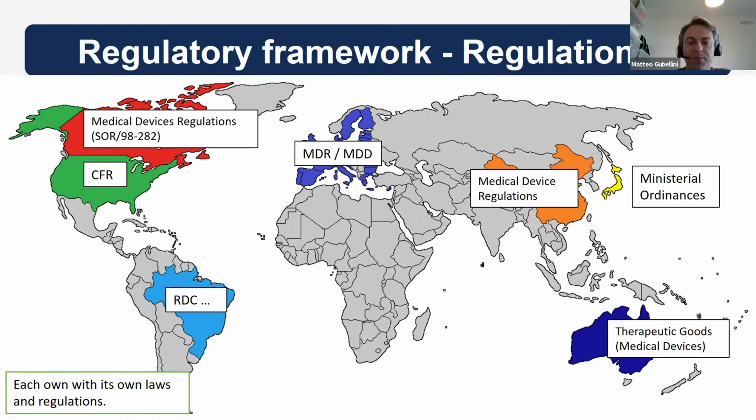They are, in most cases, promoted and signed by the government. In Europe, it was the European Parliament. But this is very much country or jurisdiction specific, and something that is required in one jurisdiction is not necessarily required in other ones. They go into a level of detail like classification of devices, post-market surveillance, the way to register a device, the way to report adverse events, complaints, things like that, which are very specific to each country, or the fees to pay. What are the fees to register a device?